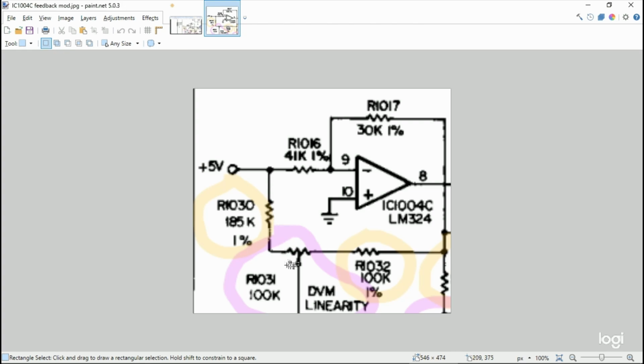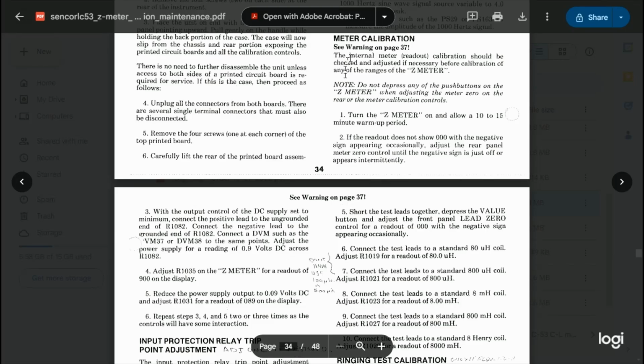As it turns out, this particular trim pot is in the middle of a feedback loop on IC1004C, which is an op amp. And the funny part is this value and this value, R1030 and R1032, the static resistors on either side of the loop, are correct. Now this one, since it's got positive 5 volts, probably didn't change much, but the whole thing of getting the voltage around, through, from, signal, whatever, on this whole network was changed, disturbed, disrupted when I changed this to a larger value. And it turns out that I can no longer keep within any proper calibration range because of that. And it looks like this is part of the calibration for the meter.